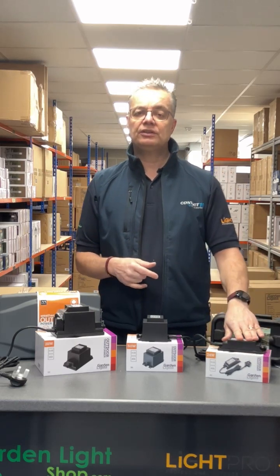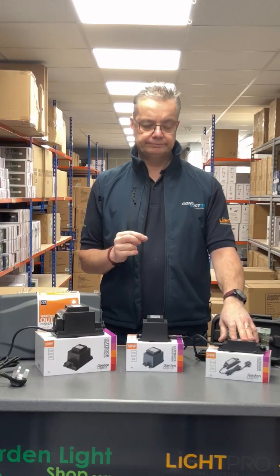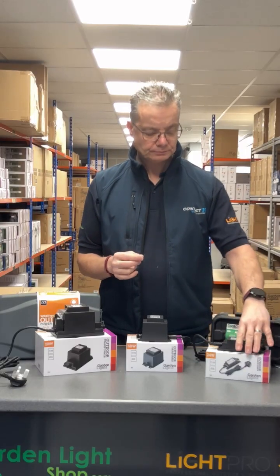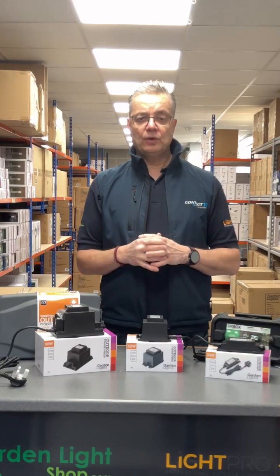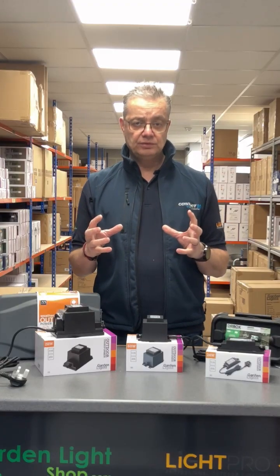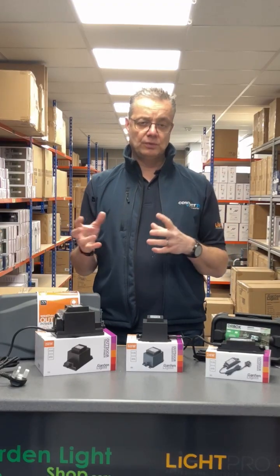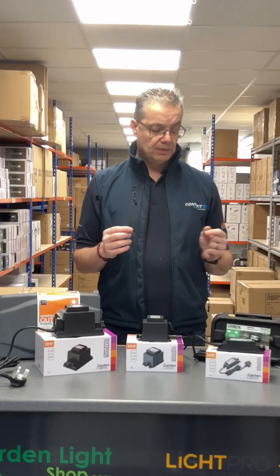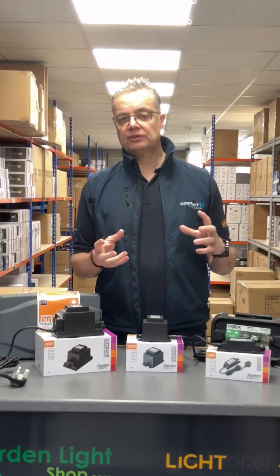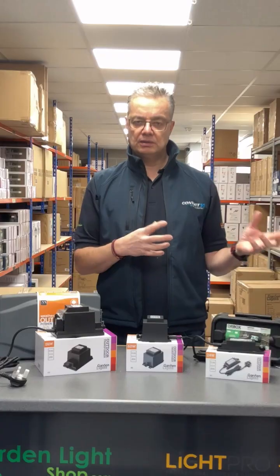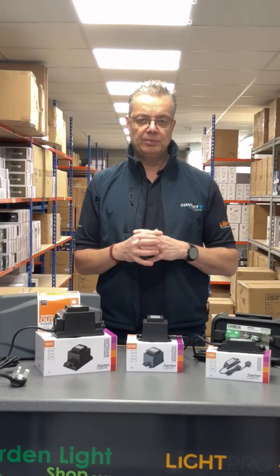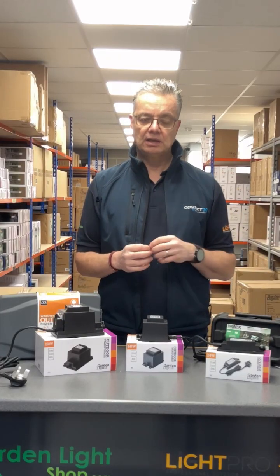This can be loaded to a maximum of 24 watts, because it's DC. That 24 watts is a combination - the lighting load you're putting on it, so that's the total wattage of all the lights, plus any 12 volt switches we do that you may need to allocate a bit of wattage out of the capacity.